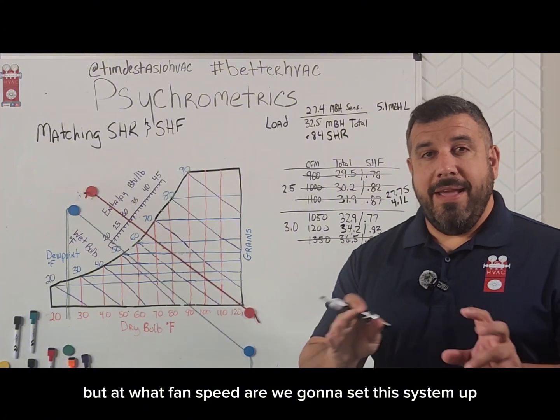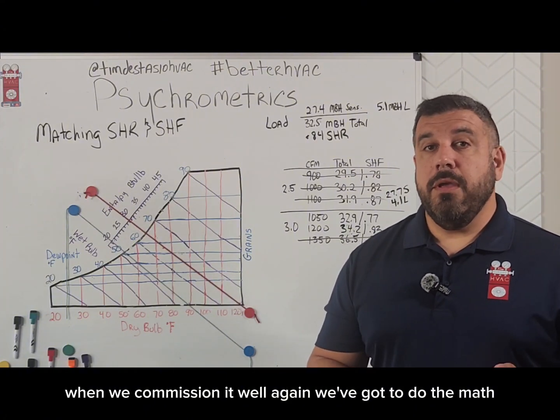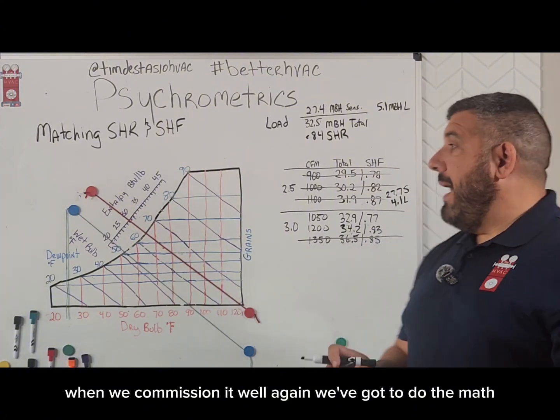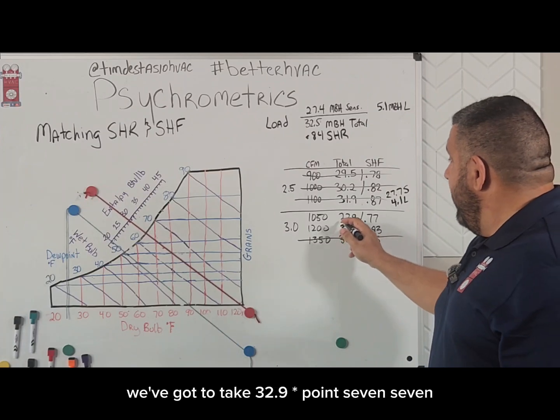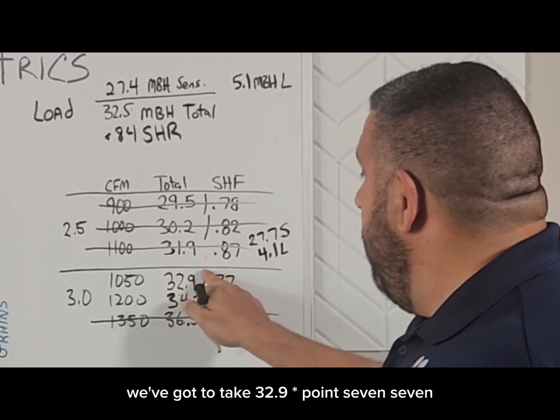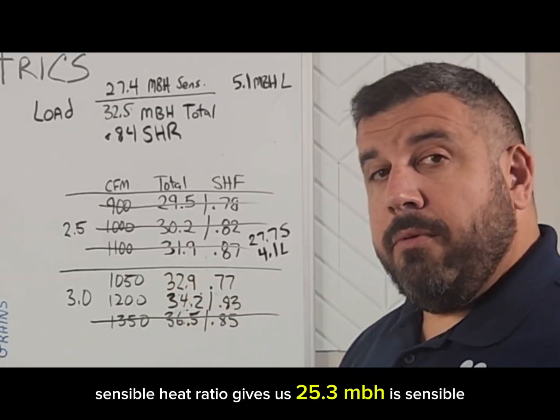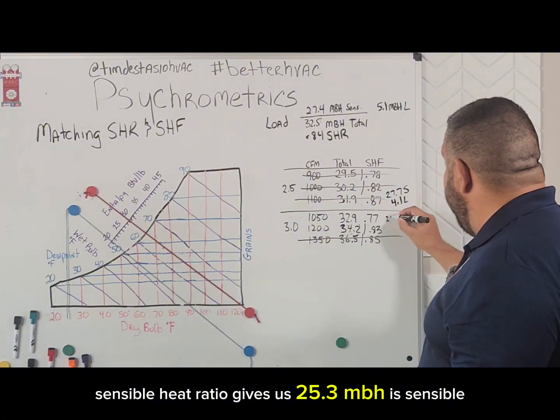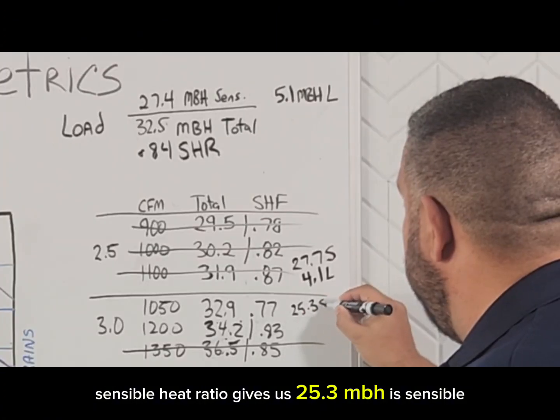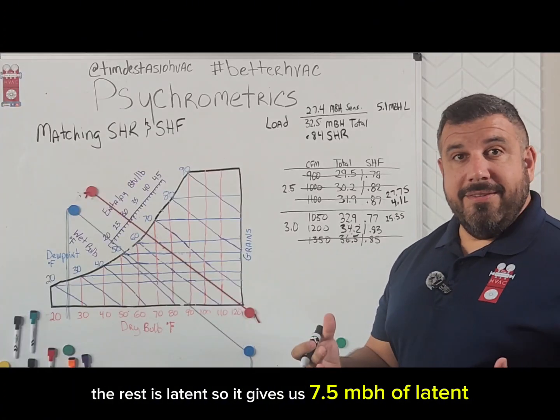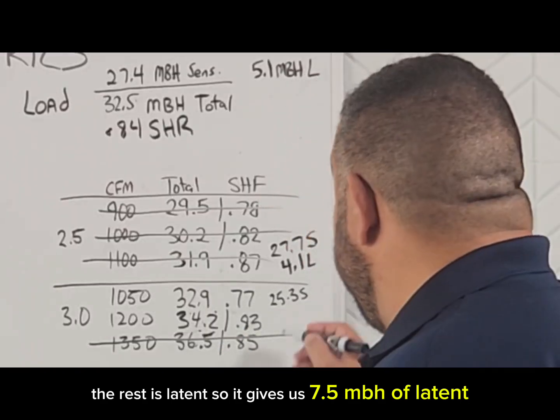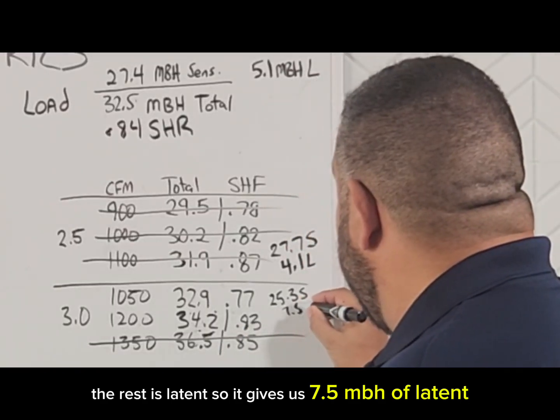But at what fan speed are we going to set this system up when we commission it? Well, again, we've got to do the math. We take 32.9 times the 0.77 sensible heat ratio. That gives us 25.3 MBH sensible. The rest is latent. So that gives us 7.5 MBH of latent.